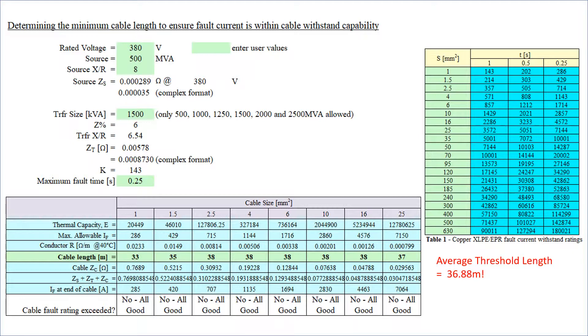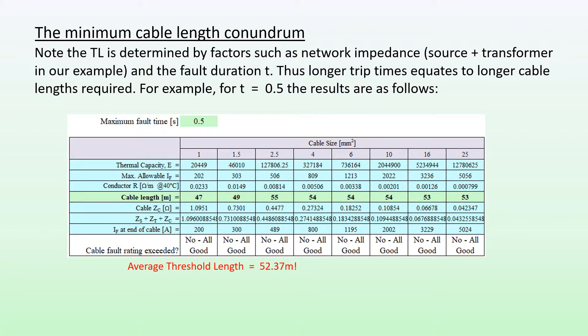Note that the TL is determined by factors such as the network impedance and the fault duration. For example, if I increase my fault time from 0.25 to 0.5 seconds, I get the following results. With maximum fault time of 0.5 seconds, I see that my threshold length for a 1 mm² cable has now gone up to 47 meters, 49 for 1.5, 55 for 2.5 mm² cable, and so on. So with a longer fault duration, I need a longer length before my fault current drops below the maximum fault current cable rating.